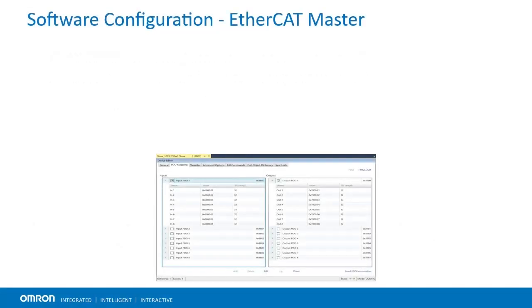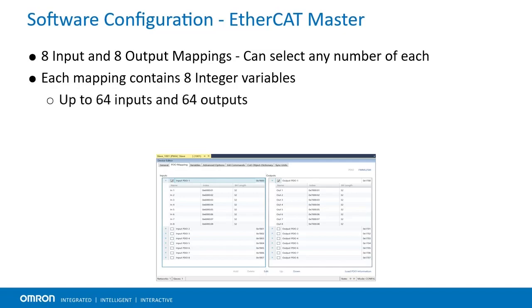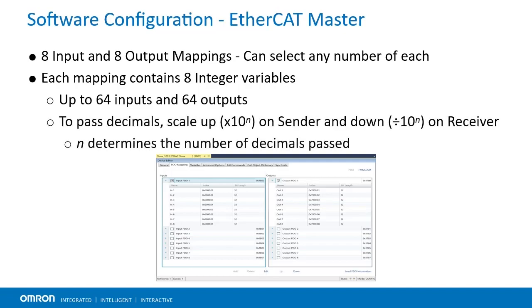Once your Slave is detected, you can select which PDO mappings you wish to use. The EtherCAT Slave ESI file allows users to enable up to 8 mappings of inputs and 8 mappings of outputs. These are not mutually exclusive, so enable as many as you need. Each mapping contains 8 variables, for a total of 64 inputs and 64 outputs with everything enabled. Note that these are transmitted as 32-bit integers, so any decimals will be truncated. If users wish to save decimal precision, they can scale up the parameter by a factor of 10 and then scale it back down in the master device before reading it, using a simple PLC on each of the master and slave devices.